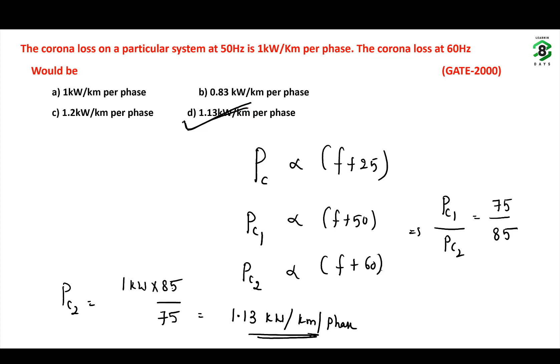If you simplify this, PC1 by PC2 equals, removing the proportionality constant, 75 by 85. We know the PC1 value is 1 kilowatt. So PC2 will become 1 kilowatt times 85 divided by 75, which is 1.13 kilowatt per kilometer per phase. So option D is the right option. Thank you.